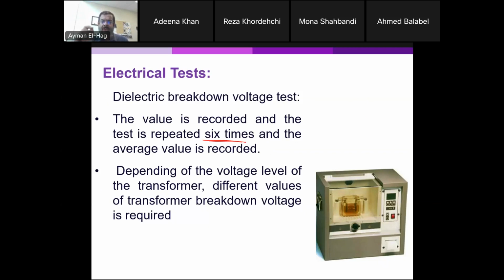So you apply the voltage, and the voltage increases until a flashover happens. Then the stirring element starts to rotate and circulate the oil. Then you apply the test for the second time, for the third time, until it reaches 6 times, and then you get the average value. So this is very standard. I used to have this piece of equipment a long time ago. You even get a printout with the 6 results and the average value of these results.